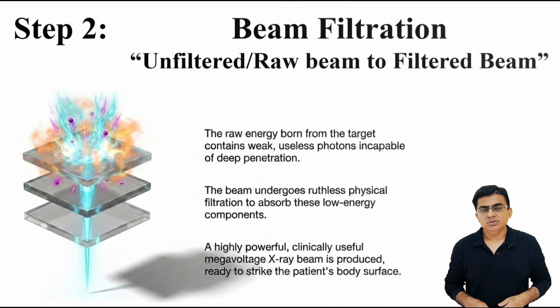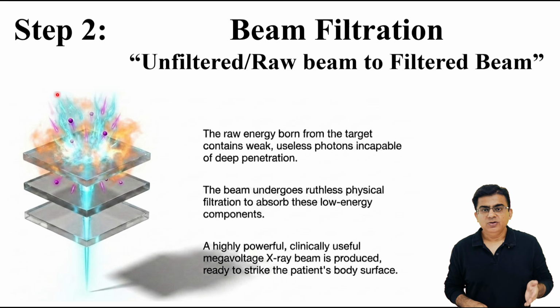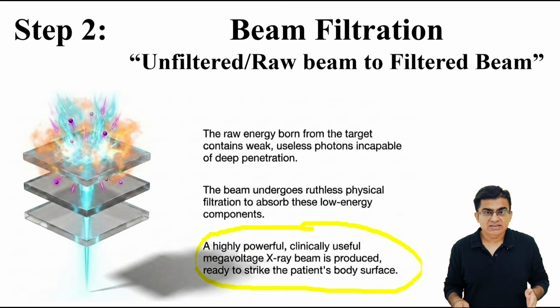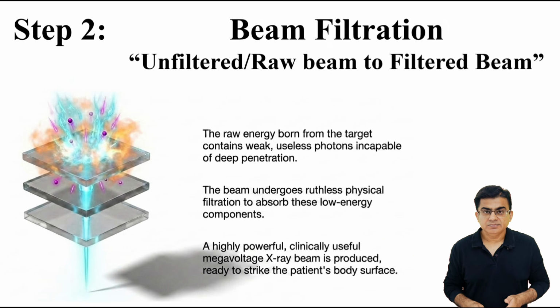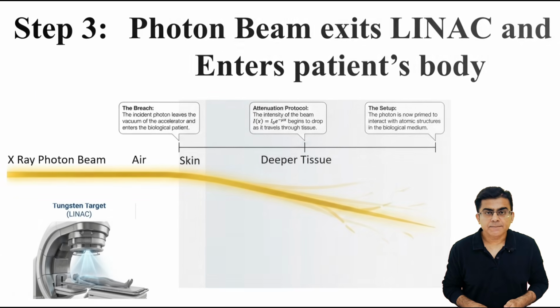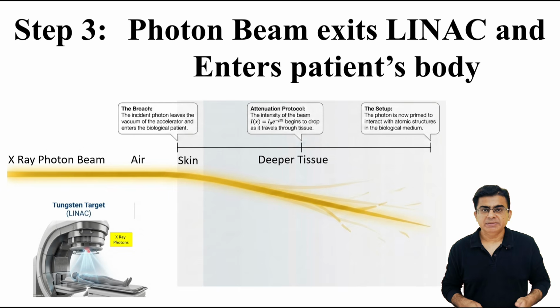This is another diagram to explain the same things. You can see the unfiltered raw X-ray beam coming from the top like this. We place a filter here. These filters selectively absorb those low energy photons. This process is called beam hardening. Now we finally have a powerful and penetrating megavoltage X-ray photon beam. This hardened beam is clinically safe and highly useful. It is now ready to exit the linac and strike the patient. Let us move on to see the third step.